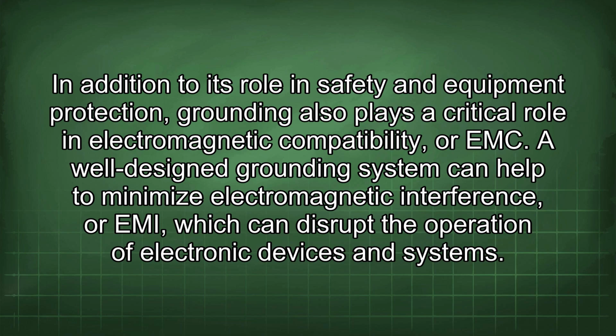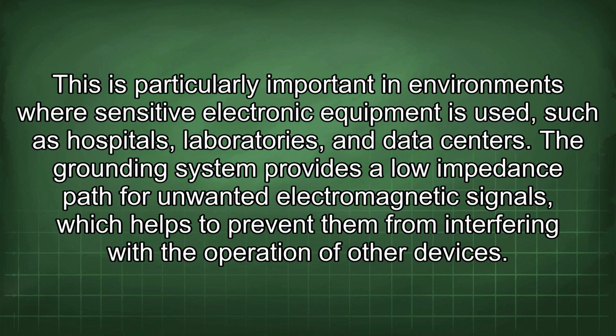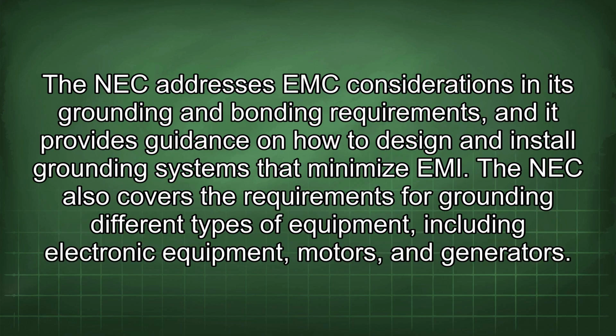In addition to its role in safety and equipment protection, grounding also plays a critical role in electromagnetic compatibility, or EMC. A well-designed grounding system can help to minimize electromagnetic interference, or EMI, which can disrupt the operation of electronic devices and systems. This is particularly important in environments where sensitive electronic equipment is used, such as hospitals, laboratories, and data centers. The grounding system provides a low impedance path for unwanted electromagnetic signals, which helps to prevent them from interfering with the operation of other devices. The NEC addresses EMC considerations in its grounding and bonding requirements, and it provides guidance on how to design and install grounding systems that minimize EMI.